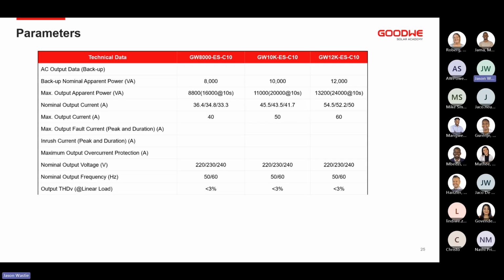The AC output data from backup. Here we allow for overloading, of double the inverter capacity for around 10 seconds. This allows for your higher peaking startup loads to work on your inverter before it gives you an overloading error. So we have some allowances on that. Note that we can constantly output 10% extra. Like I've said before, 13.2 kilowatts on a 12 kilowatt inverter, and 11 kilowatts on the 10. The max output current is 40 to 60 amps on our standard 230 volts nominal output voltage.